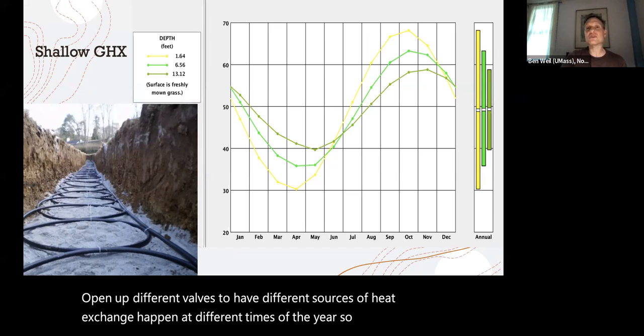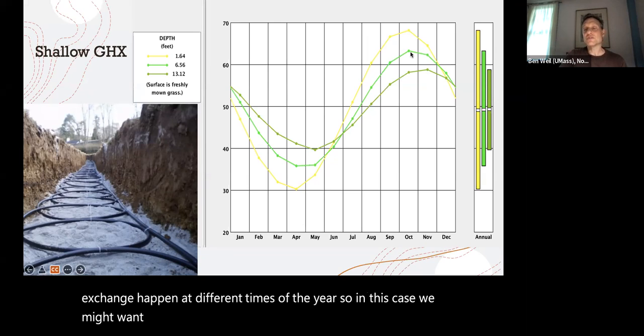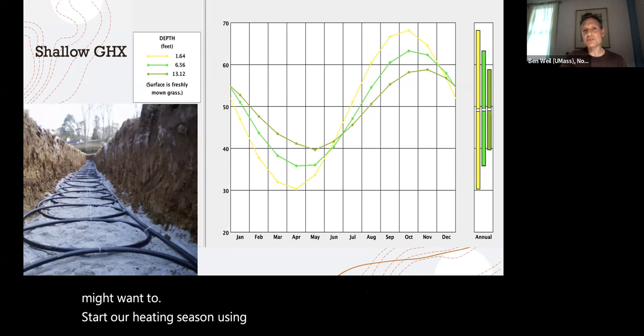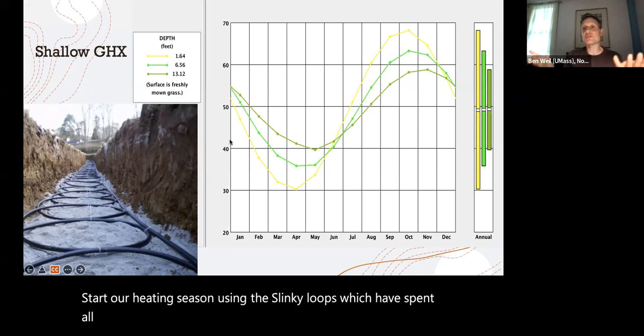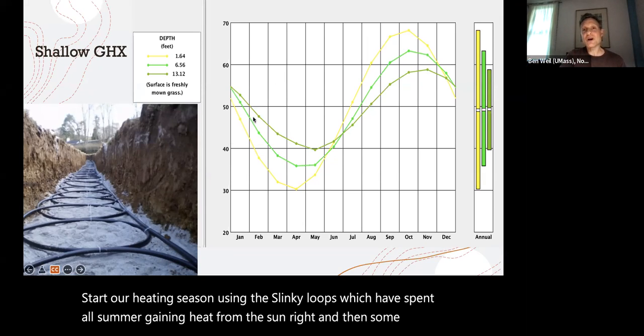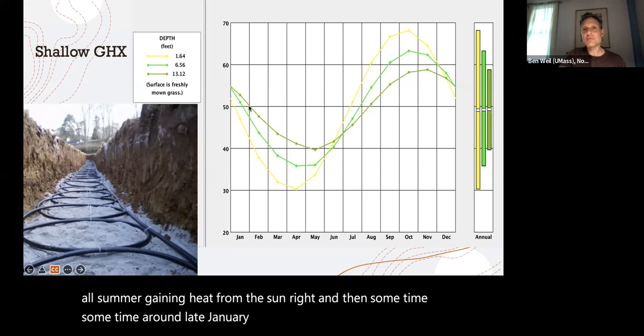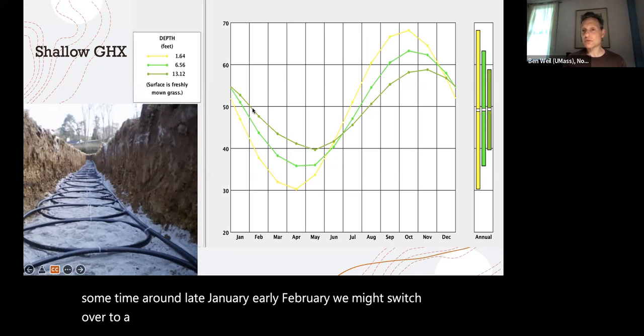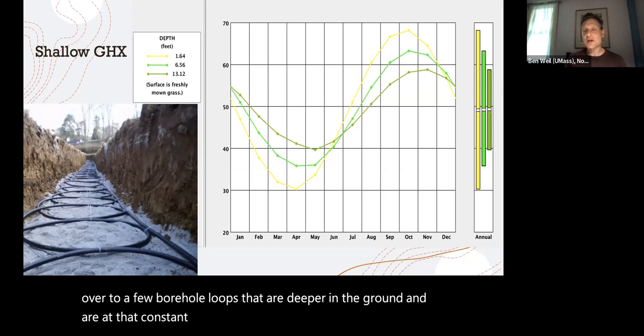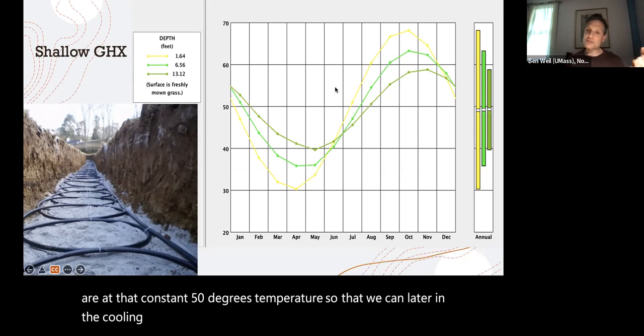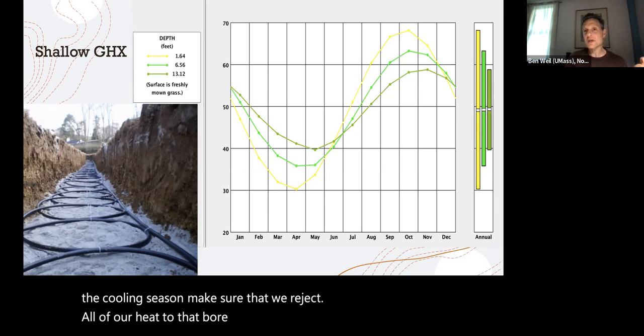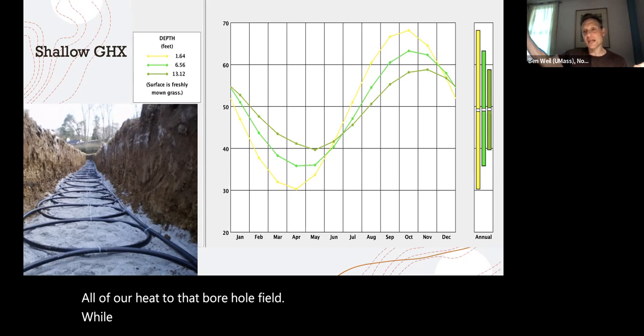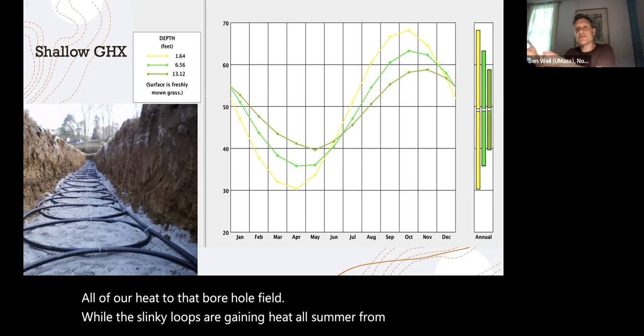So in this case, we might want to start our heating season using the slinky loops, which have spent all summer gaining heat from the sun, right? And then sometime around late January, early February, we might switch over to a few borehole loops that are deeper in the ground and are at that constant 50 degrees temperature, so that later in the cooling season we can make sure that we reject all of our heat to that borehole field, while the slinky loops are gaining heat all summer from the sun. And then we switch over to the slinky loops again.